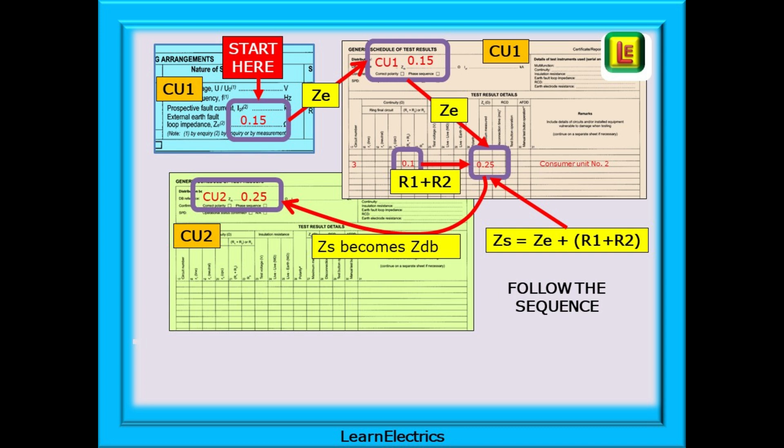Now add the ZE or ZDB to the measured R1 plus R2. 0.15 plus 0.1 gives us 0.25 ohms for CU2 ZS. Then on consumer unit number 2 test results page write in 0.25 ohms for ZDB.